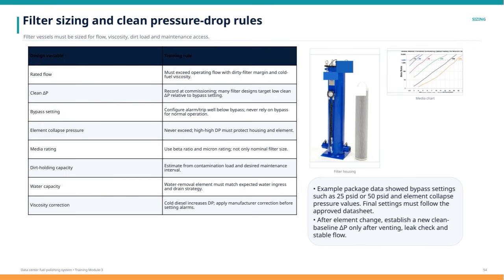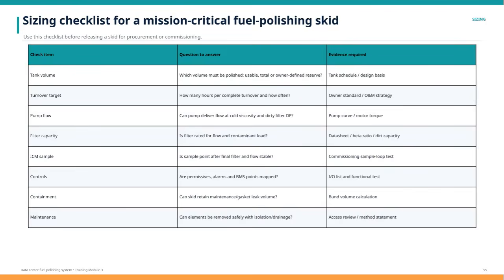After any element change, be sure to vent, leak check, and establish a new clean delta P baseline under stable flow conditions to ensure accurate performance monitoring. Finally, always refer to the approved datasheet for final settings like bypass pressures and element collapse values to ensure compliance and safety. Before moving forward with procurement or commissioning of a mission-critical fuel polishing skid, it's essential to go through this sizing checklist to ensure everything is properly addressed.